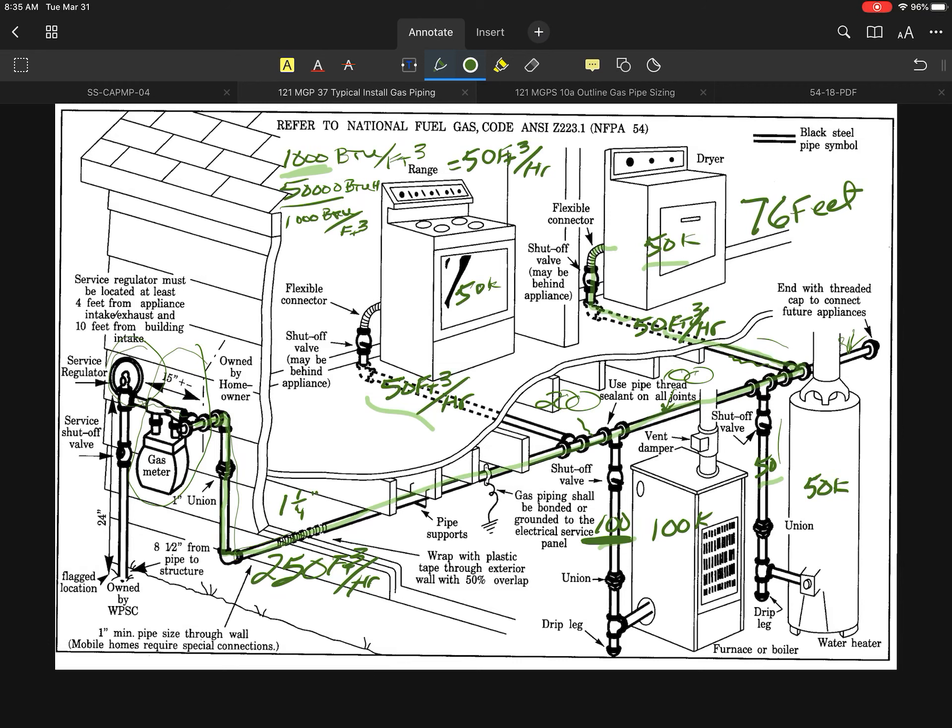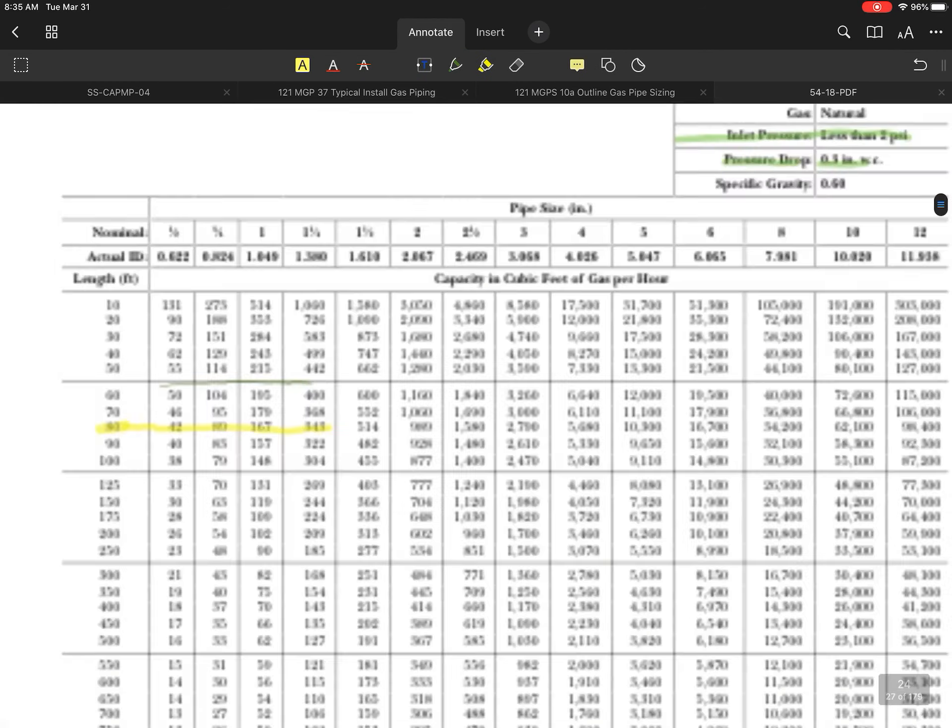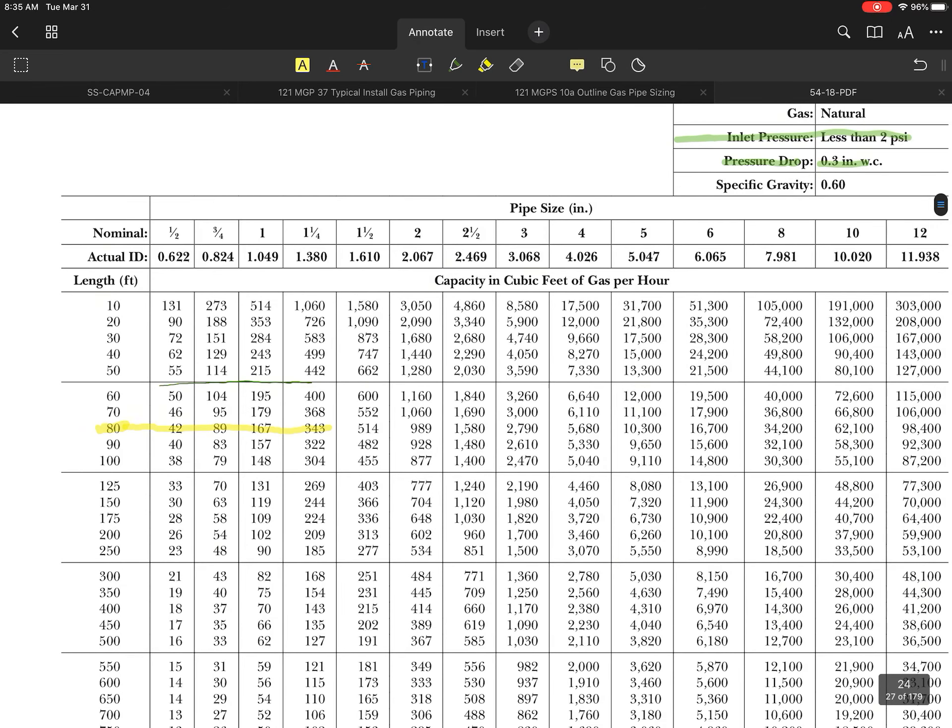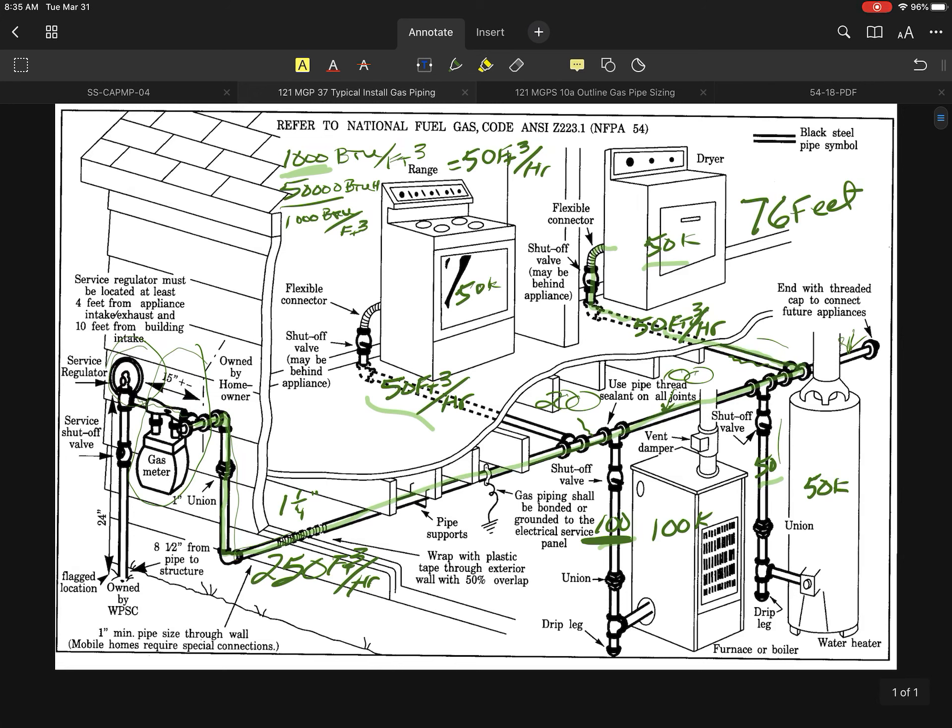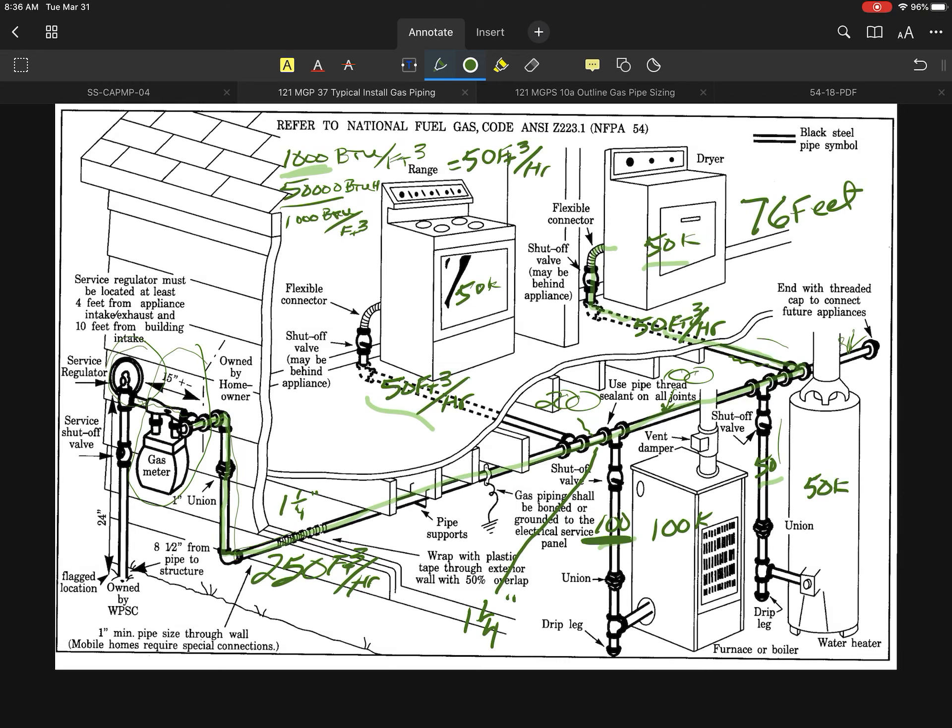Going back to my picture, this pipe right here is going to have to be 1.25 inch. When I move on into this next section, I'm going to get rid of 50 cubic feet of gas, and then I'm left at 200. If you remember that section we addressed earlier when I looked at the code, we can't even think about switching until we get down to 167, so this one here is going to have to be 1.25 inch as well.